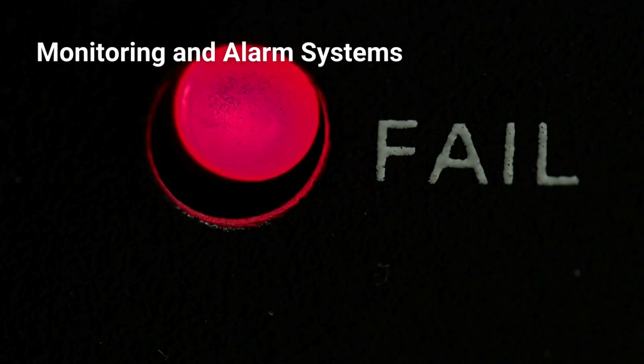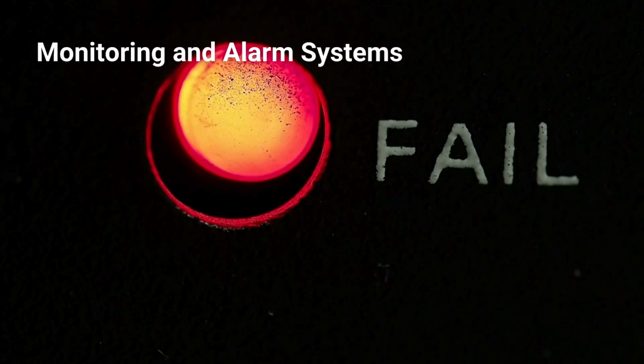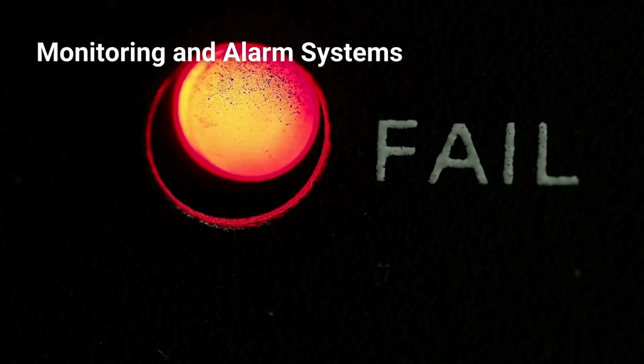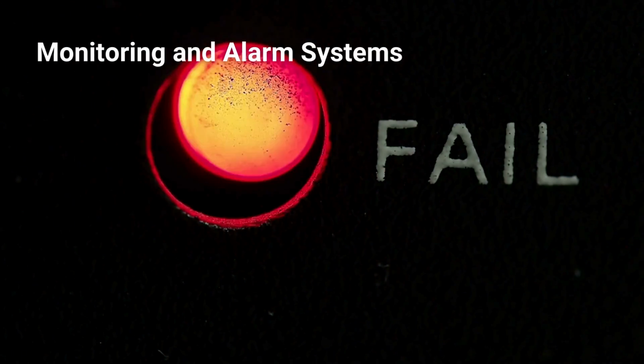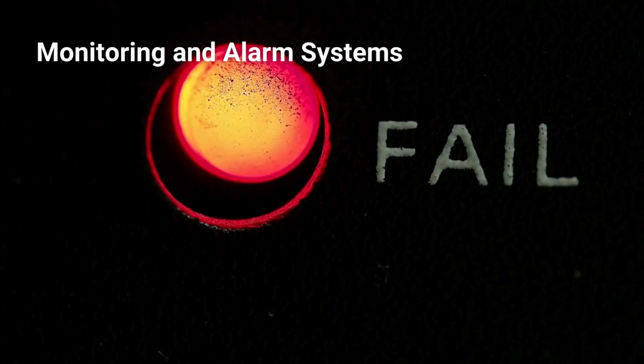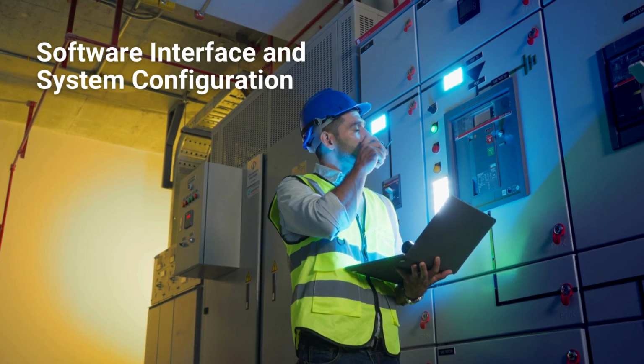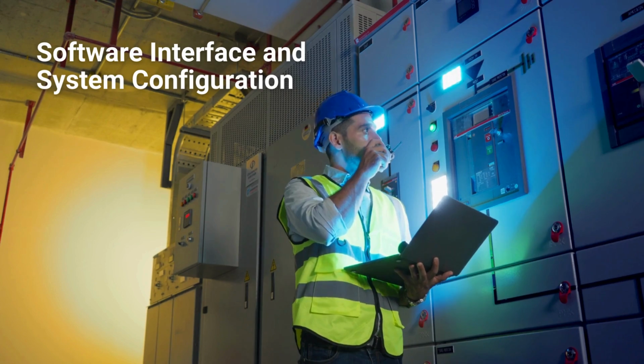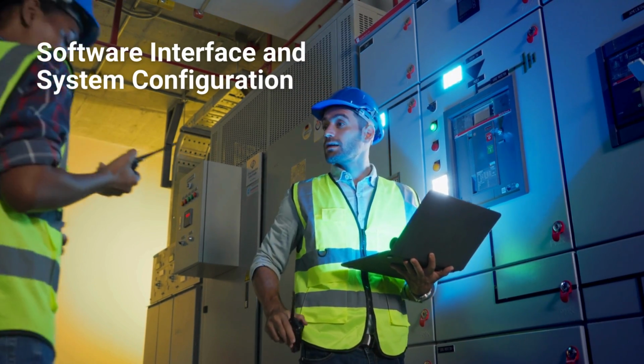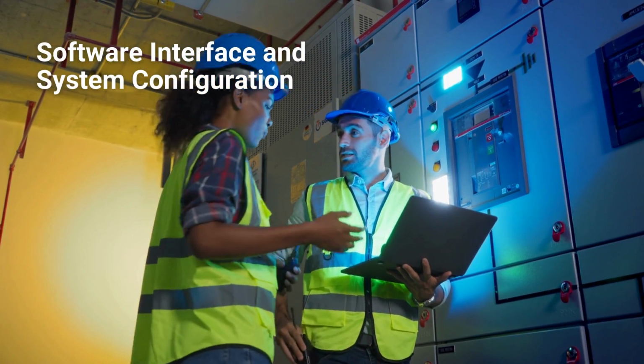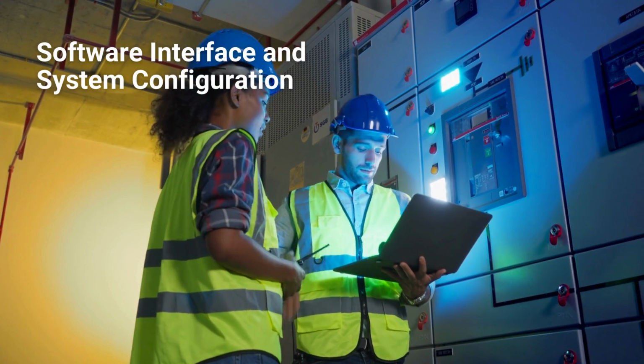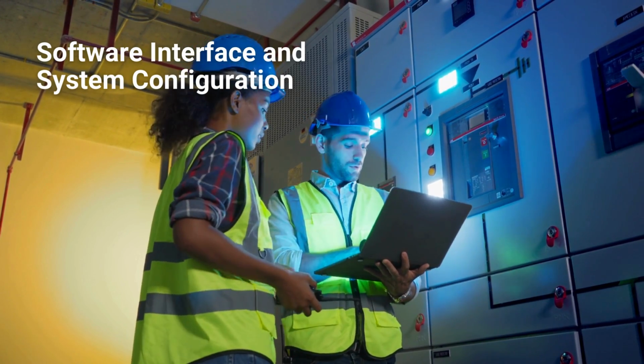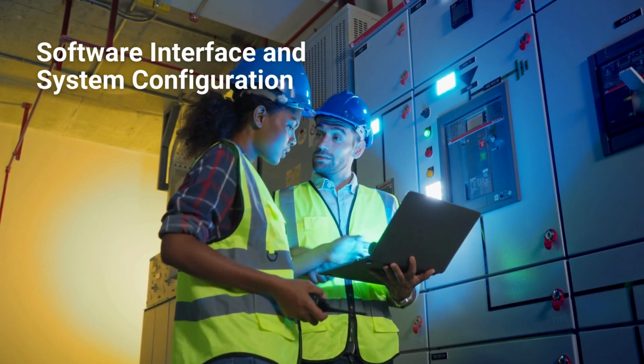Monitoring and alarm systems continuously monitor the health of the entire EVC system, generating alerts for faults, power failures, or line issues. This ensures that any issues are identified and resolved before they can impact system performance. Software interface and system configuration is used to configure the EVC system during commissioning and to monitor system health during operation. It allows the customization of communication zones, call priorities, and system responses to different emergency scenarios.